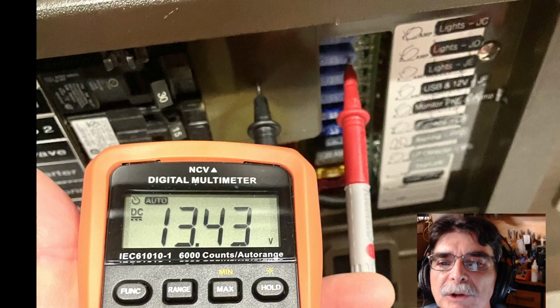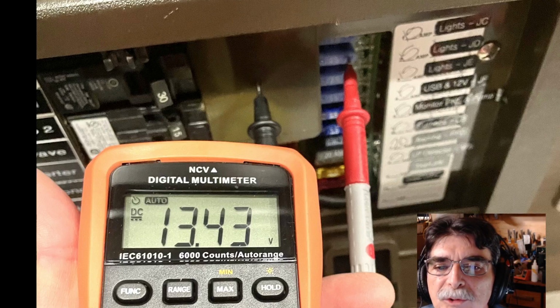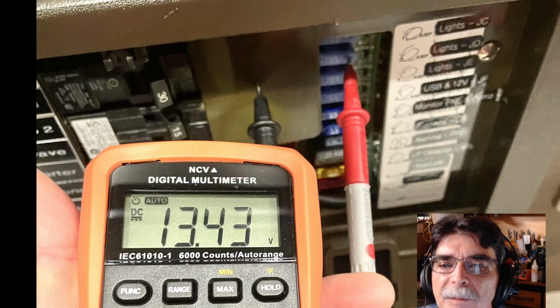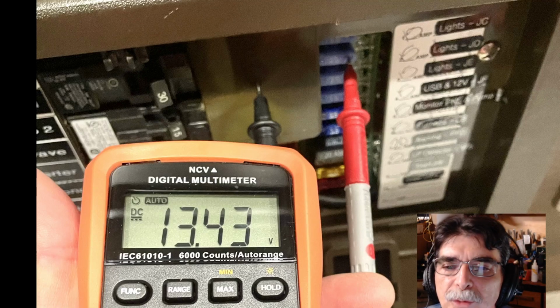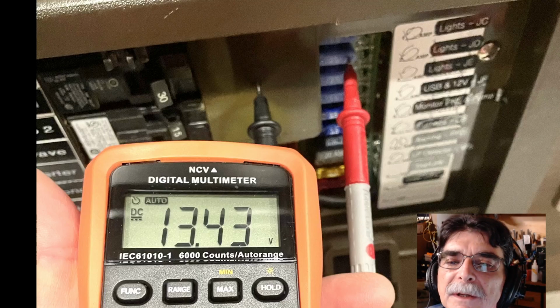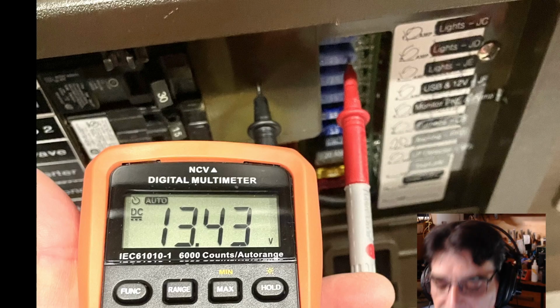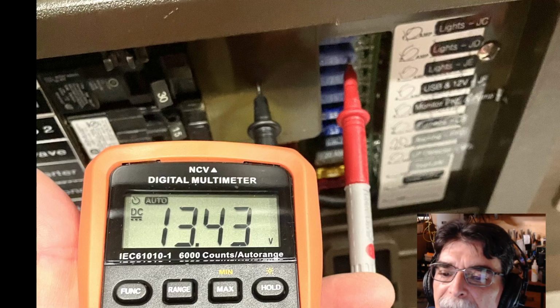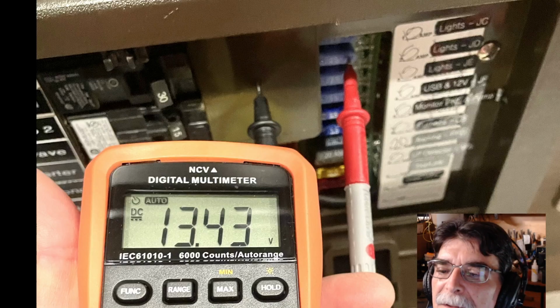I drilled an 1/8 inch hole right on top of one of those two ground screws we discussed earlier, because there's no way to find a ground without taking off the WFCO cover. It's easy to just put your probe on one of those two Phillips head screws at the top and use that as ground, then use your red probe on any of the fuses, since they'll all carry battery voltage. So here I'm measuring the battery voltage at the panel.